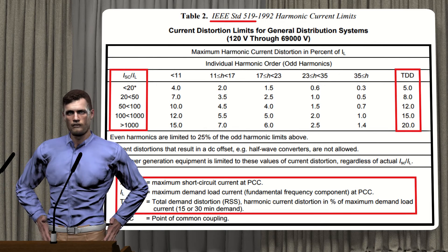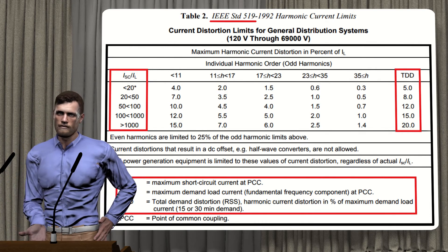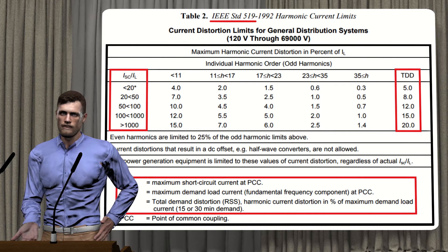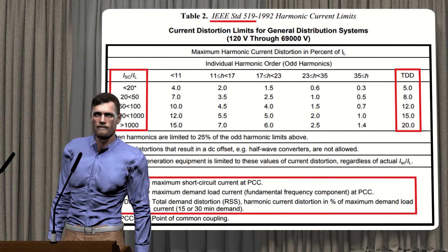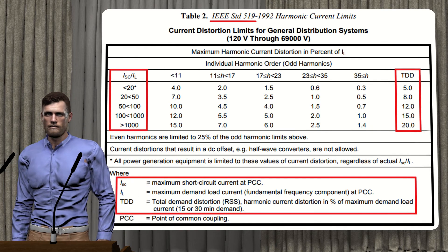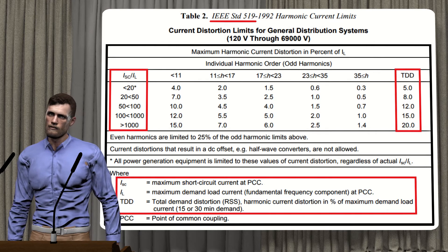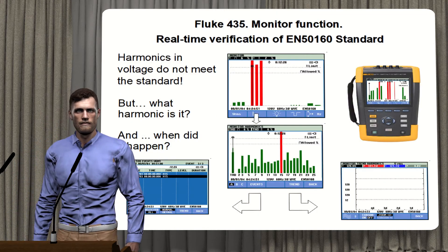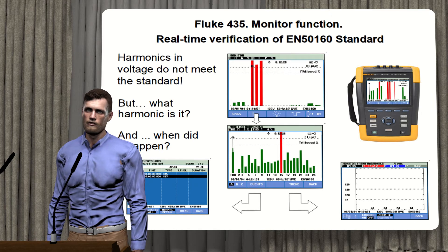As was the case for the voltage THD, these values are specified for the common coupling point, or PCC. After having seen all this, it no longer seems so complicated to carry out a harmonic analysis. We just have to make the measurements and compare them with these limits. But to further simplify the technician's work, and avoid having to remember the limits of each voltage harmonic and the voltage THD, analyzers such as the Fluke 435 have the EN50160 standard memorized.